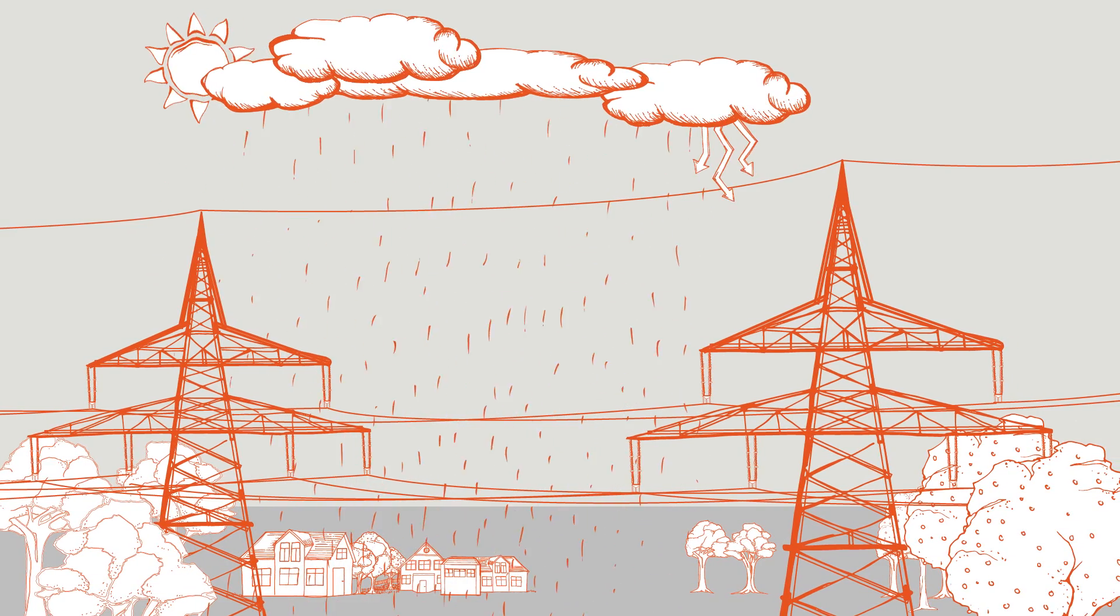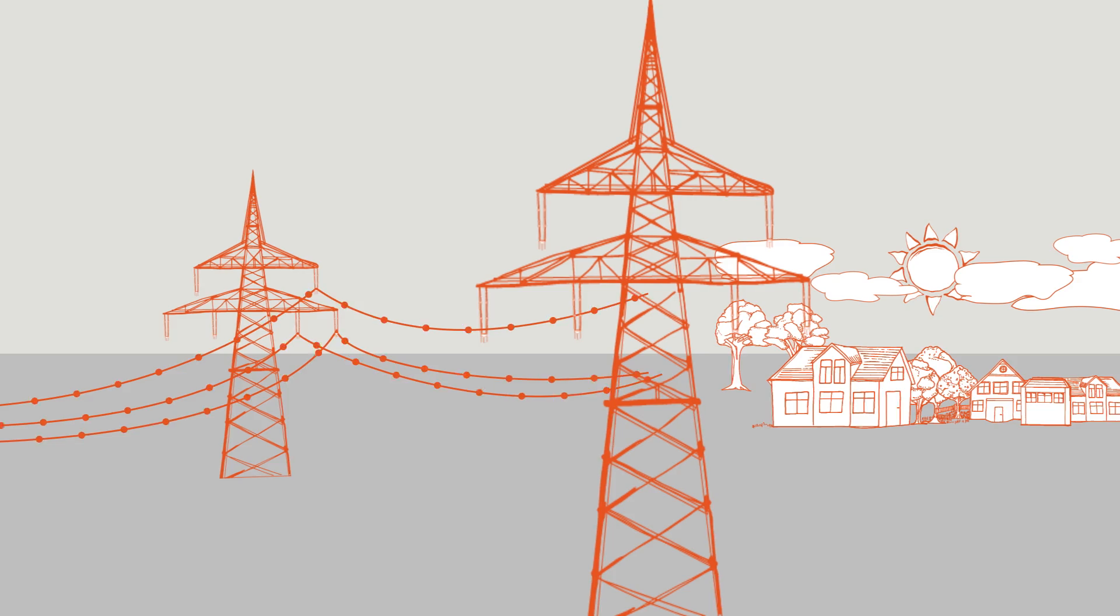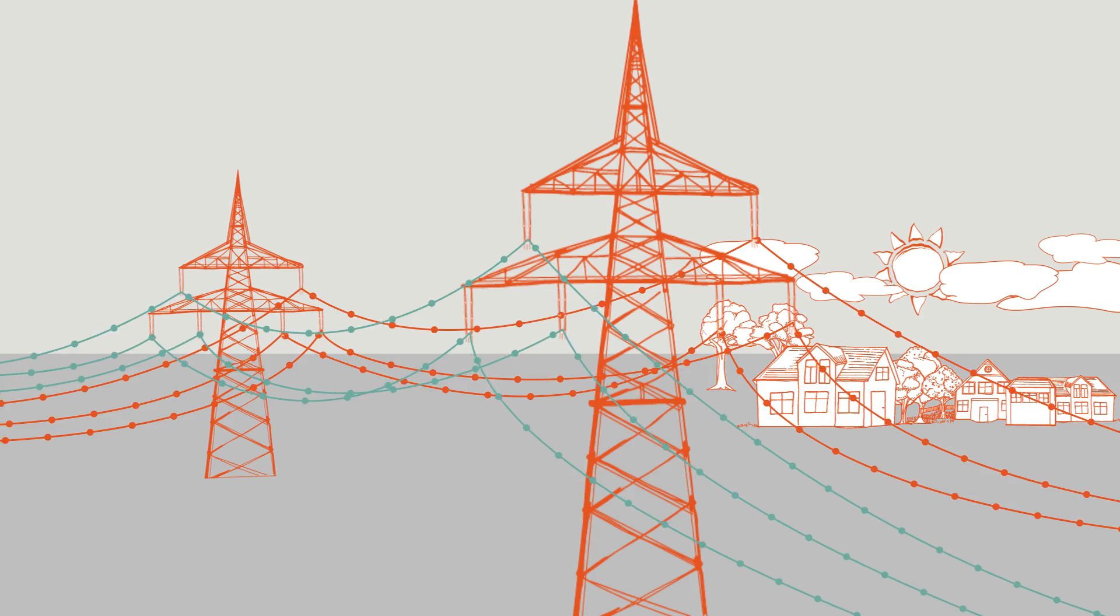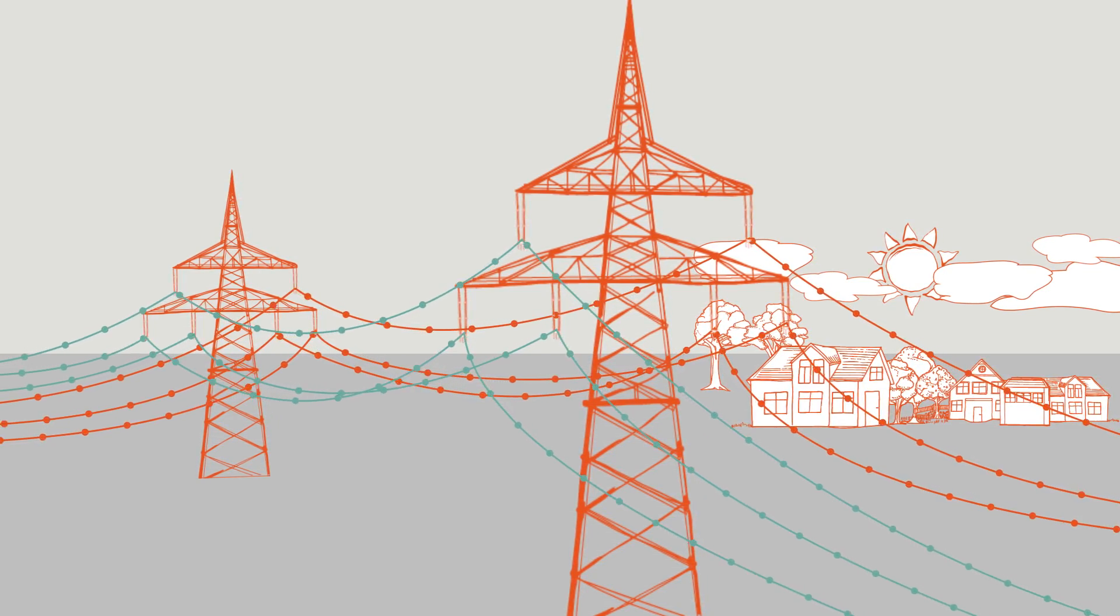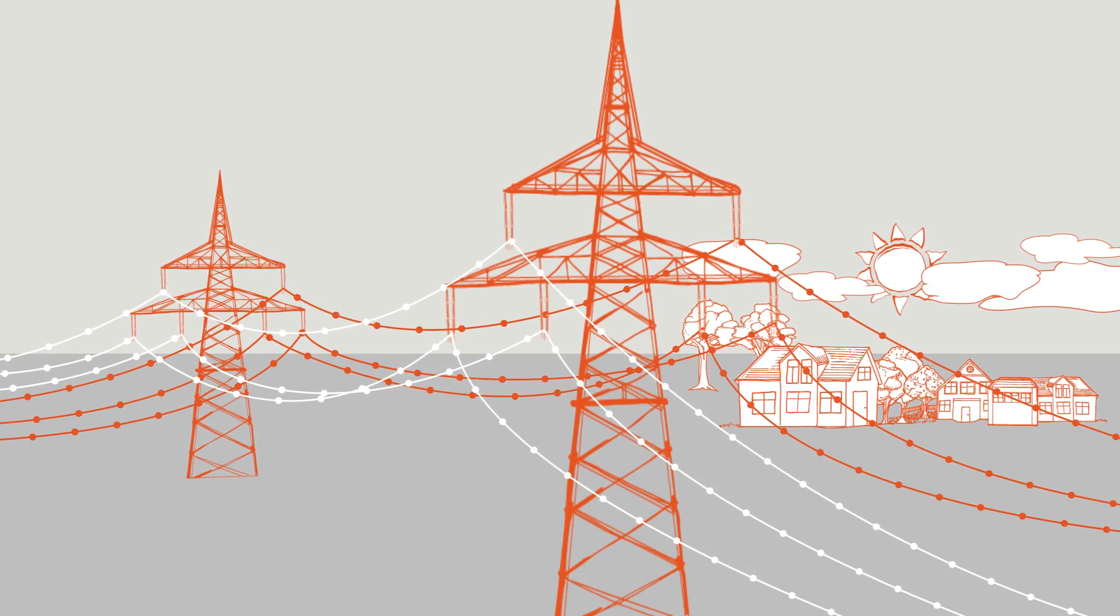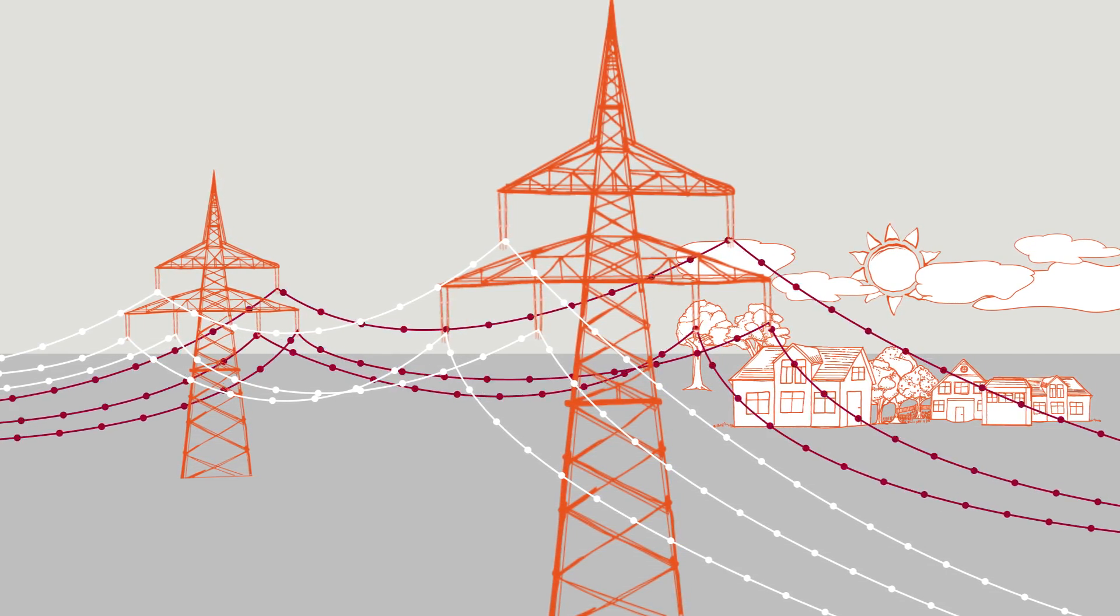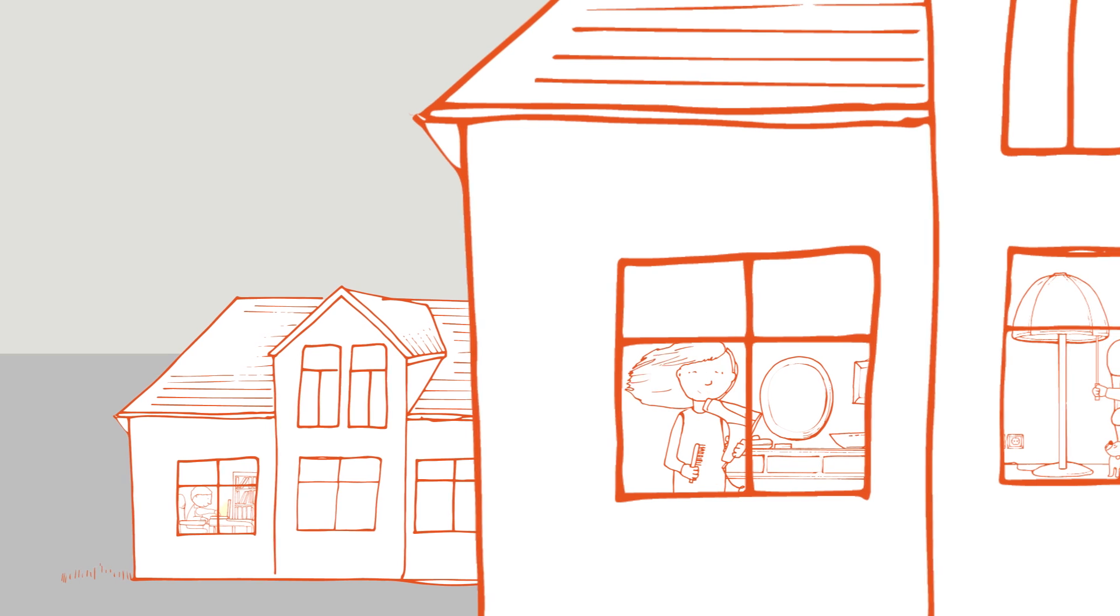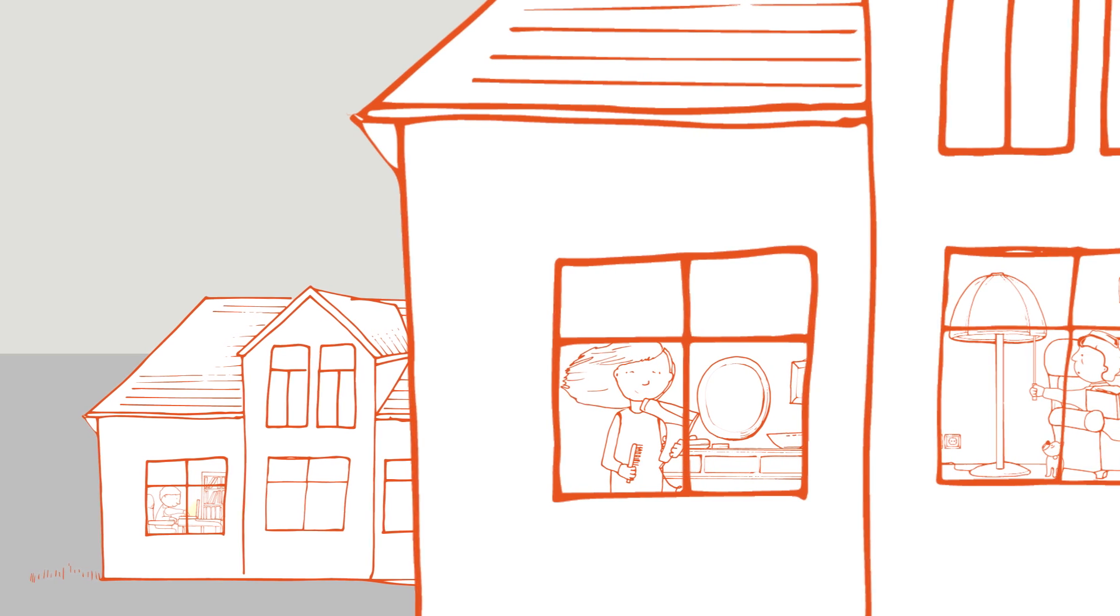The overhead lines of the 50 Hertz high-voltage grid are usually equipped with two electrical circuits. Electricity flows on the left and the right side. If one system, or even the entire line, fails, the rest of the power grid ensures the secure and uninterrupted electricity supply. This securing principle is called N-1.